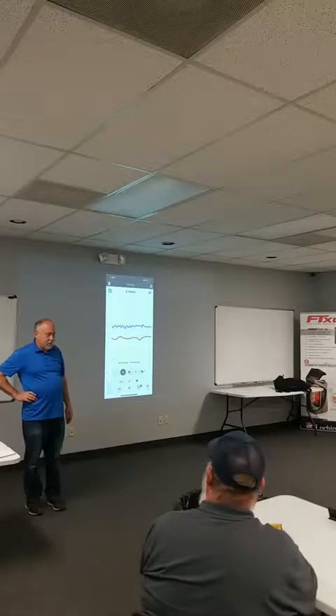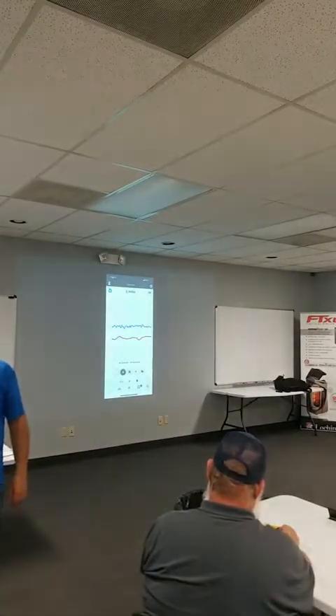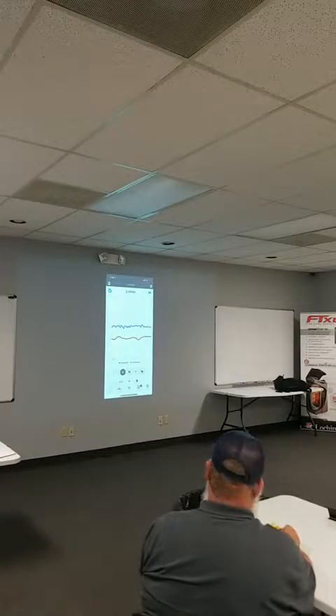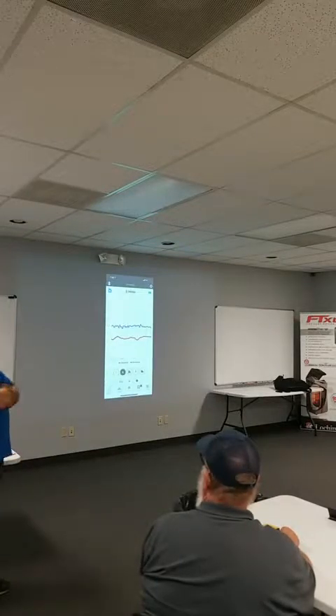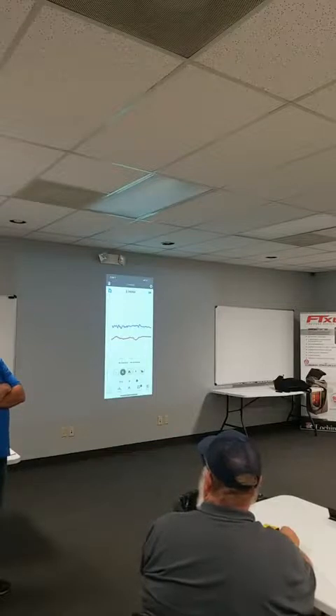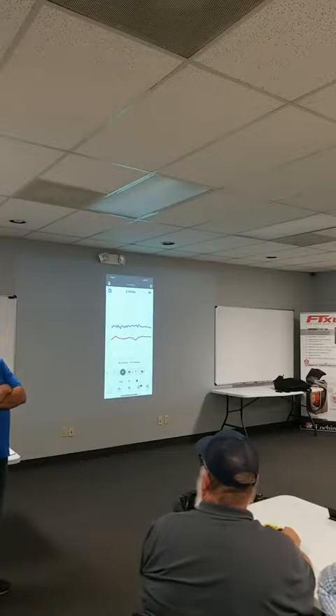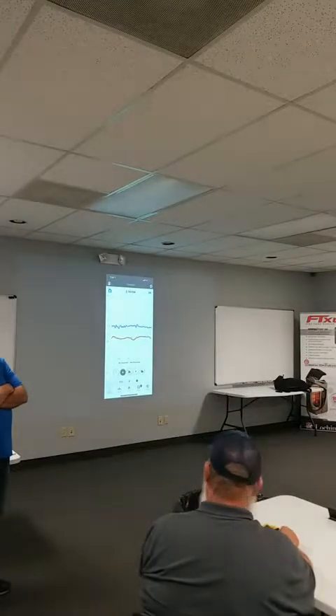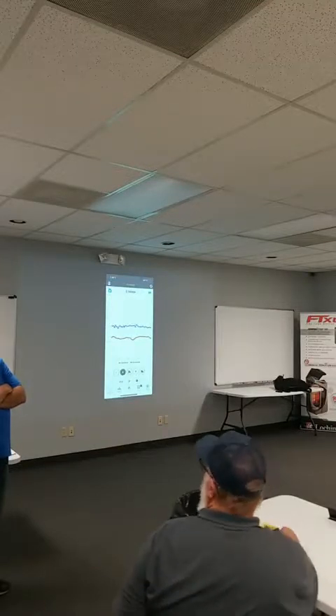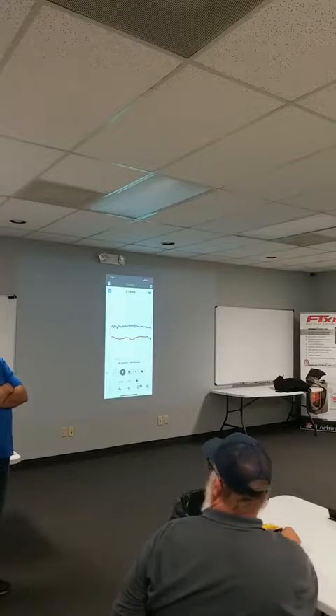Have you seen high subcooling as more common since the microchannel coils came about? Well, is this microchannel out here? Yes. And this is why you're seeing it. Normally you would never see this on a regular copper coil, because microchannel's so goofy. I didn't realize it was microchannel, because when you say you pulled the charge out and weighed it in, microchannel condensers have different superheat or subcooling targets depending on the temperature. You could very well, because the coil is highly efficient on a mild load, have very high subcooling like this, because it's getting closer to the ambient temperature. So you'd have lower approach and higher subcooling, where on a hotter day it's going to be just the opposite. The subcooling will start to drop down.